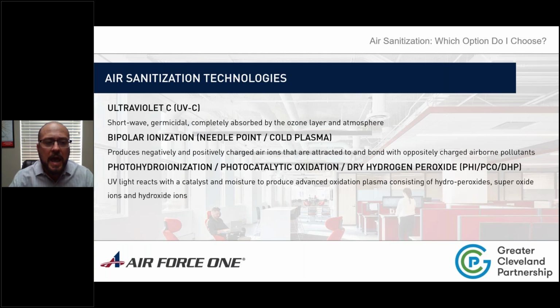Now one that most people familiar with any research recognize is bipolar ionization. There are a couple ways to create it—sometimes called needlepoint bipolar ionization, sometimes cold plasma, and some other names, but the technology does similar things. It produces negatively and positively charged air ions that are attracted to and bond with airborne pollutants, neutralizing them. The pros are there's typically not a lot of ongoing maintenance other than periodically cleaning the units, because none of these solutions get rid of dust—dust is always going to be an issue. The one drawback I see with bipolar ionization alone is its short lifespan, but I'll leave the more technical aspects to Brian.